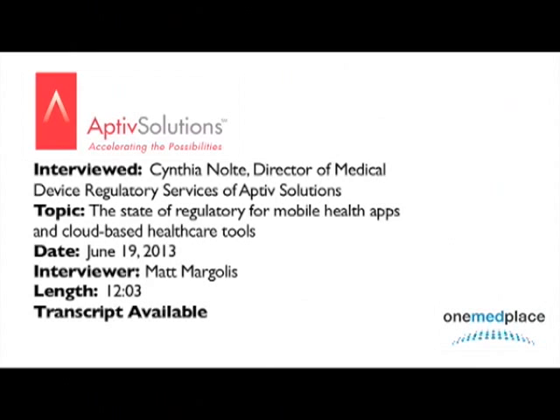Important takeaways from this project from outside are a clinical study was required, and each platform, be it an iPhone or Android or any platform, FDA would expect to see evaluated separately. I don't think that means you have to go all the way back to the clinic, but I do think that it means every platform FDA would consider a separate medical device, and you would have to do your due diligence in terms of looking at the ability of this mobile platform to support the software.